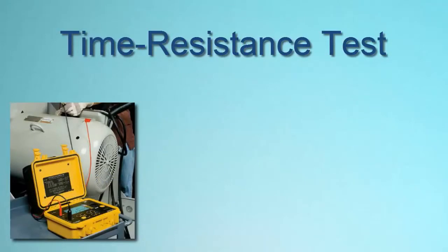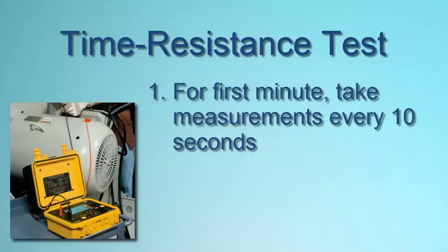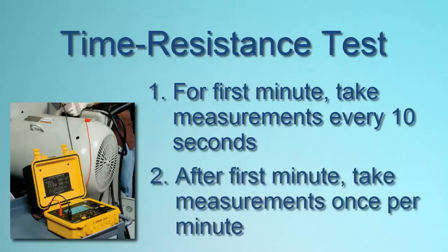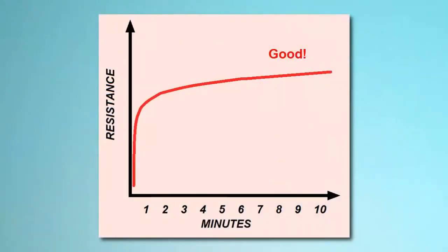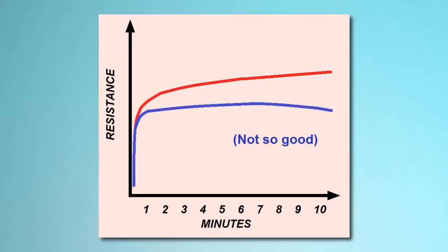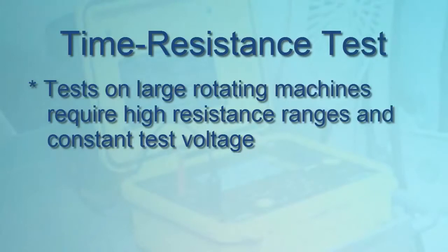Another insulation resistance measurement method is the time resistance test, also referred to as the dielectric absorption test. It involves conducting a 10-minute test. For the first minute — during which absorption current will have the highest effect on resistance — measurements are taken every 10 seconds. After the first minute, measurements are taken once per minute. When you plot the results, you should see a curve that rises relatively rapidly at first and then continues to gradually rise throughout the testing period. If instead the curve is relatively flat or begins to turn down as the test progresses, moisture, dirt, or other factors may be compromising your insulation. Time resistance tests on large rotating electrical machinery, especially systems with high operating voltage, require high insulation resistance ranges and a very constant test voltage. Since this test provides meaningful results within a single 10-minute duration, it is relatively independent of temperature.